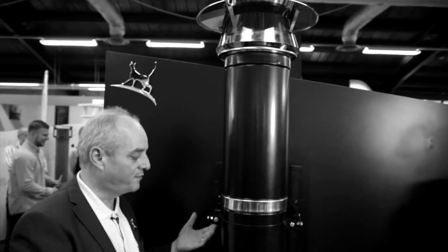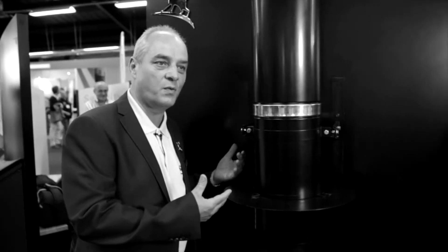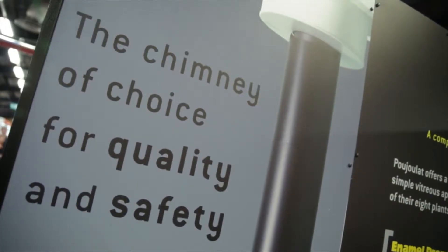Therminox is very strong — it has no more than 4m between brackets, it can do 16m off one base support, and you can have 3m freestanding. In our view, it is the best twin wall chimney in the market today.